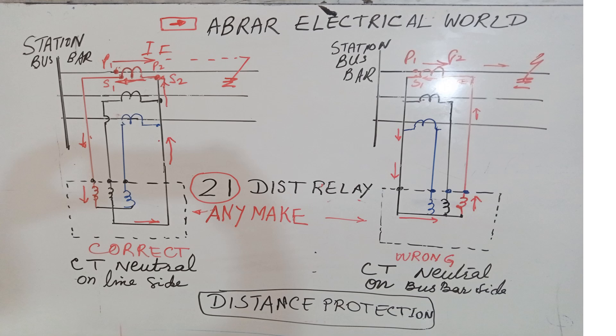These CTs are in the high-voltage yard. The connections will come to a terminal block in the control room or protection panel, and from there you connect the distance relay. Whenever there is a mal-operation of the relay, please check these connections to ensure they are made correctly — not like the wrong diagram. In summary, for the protection of a line, you should always make the CT neutral on the line side. Otherwise the relay will mal-operate and the direction will be reversed.